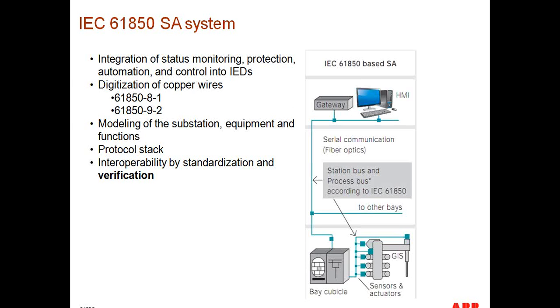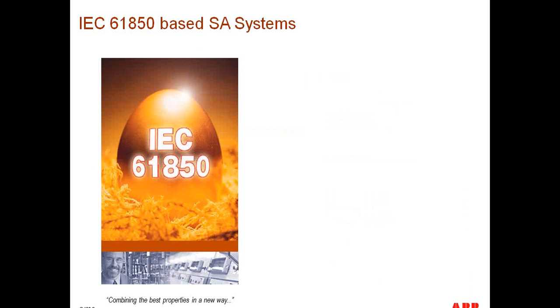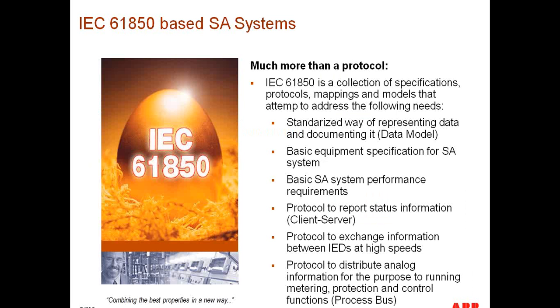This is a protocol that functionally, in principle, is somewhat similar to DNP or Modbus, where you have an IED, and the IED is collecting information. That information is transferred over to a higher level system, or to a master, in the form of a protocol. And in this case, IEC 61850 defines this ClientServer protocol as part of 8-1.